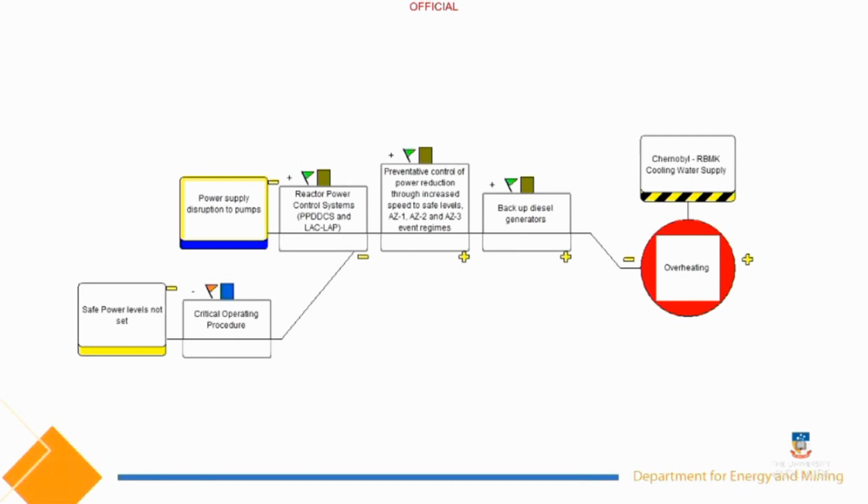In other words, a switch which would not have allowed the reactor to drop below the 300 megawatt thermal power range. Because he forgot to press that, the reactor automatically went down to zero, or was heading towards zero power, which caused the xenon poisoning. Because the reactor was losing power, xenon was being generated, and it was just poisoning the reactor.